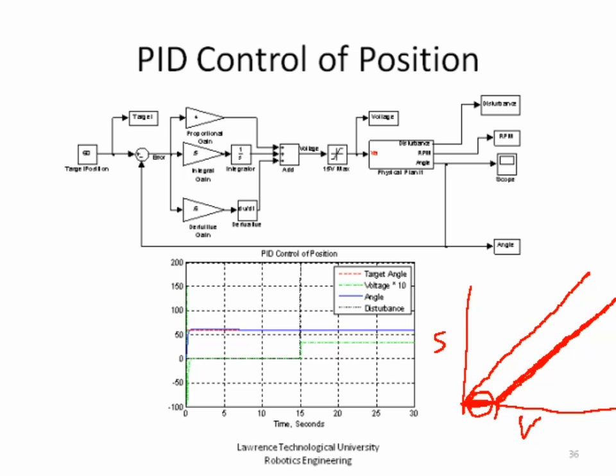Sometimes that can cause you problems. There's different ways to fix it. One is to just try to add this much to the controller output all the time, either positive or negative. So you'd always add this much to the controller output to try and overcome that. That works if this dead band is consistent. If it's variable, that's not such a good thing, you can maybe put half of it in there or three quarters of it. Another thing you can do is add this little bit of integral gain, but just keep the gains low, so it integrates very slowly, put some kind of saturation or clips on that integrator so it doesn't get too big and doesn't start destabilizing it.